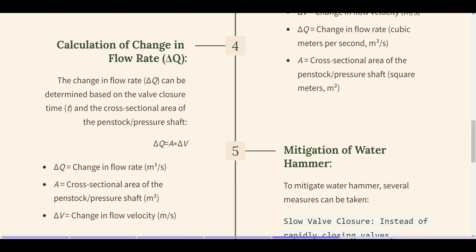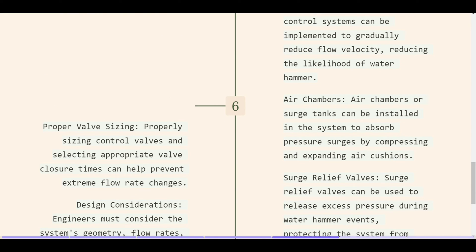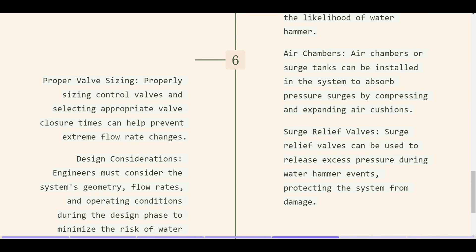Mitigation of water hammer: slow valve closure — control systems can gradually reduce flow velocity, reducing the likelihood of water hammer. Air chambers or surge tanks can be installed to absorb pressure surges by compressing and expanding air cushions. Surge relief valves can release excess pressure during water hammer events, protecting the system from damage. Proper valve sizing and selecting appropriate valve closure times can help prevent extreme flow rate changes. Engineers must also consider the system's geometry, flow rates, and operating conditions during the design phase to minimize the risk of water hammer.